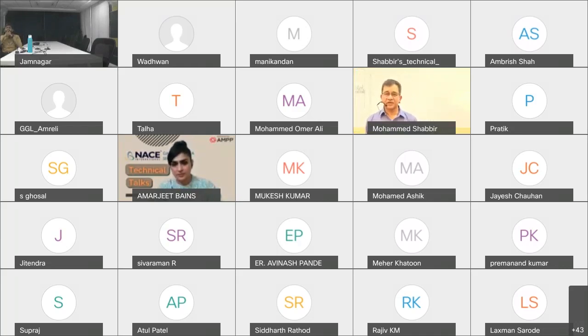These are words that sound very nice to the ears, but in the field we know the difficulties - how technicians struggle to get the rectifier up and running. Sometimes rectifiers are not attended to even for several months, which is definitely not desirable. That is the reason most Middle East and Asia Pacific countries go with manual circuits. Manual rectifiers are very easy to repair. We really don't need auto rectifiers because the soil chemistry is fixed, the requirement is fixed, and there will not be any variation requiring auto control.